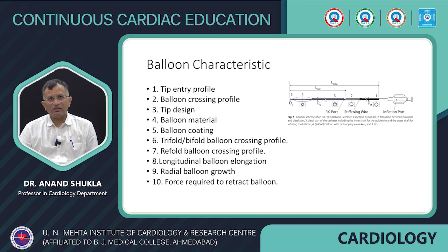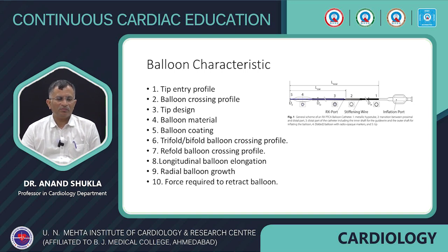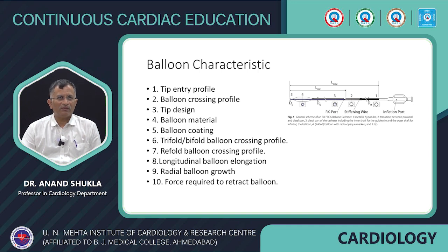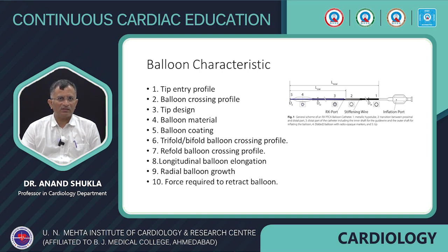Looking at balloon anatomy, there is a hub and distal tip. The key characteristics to look for in a balloon include: tip entry profile, how small the balloon crossing profile is, diameter, tip design — whether tapered or non-tapered — balloon material, whether balloon coating is present, and when the balloon is folded, whether it is trifold or bifold, since trifold requires a smaller crossing profile. Once the balloon has been used, the re-fold crossing profile is also important, as we sometimes reuse balloons to cut down cost. While inflating, one should consider longitudinal balloon elongation, radial balloon growth, diameter increase, and the force required to retract the balloon.